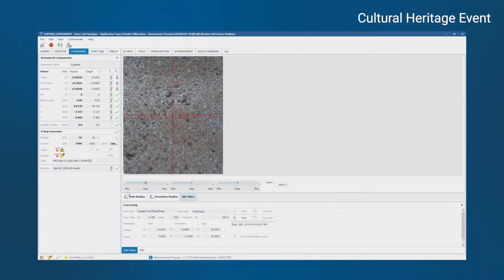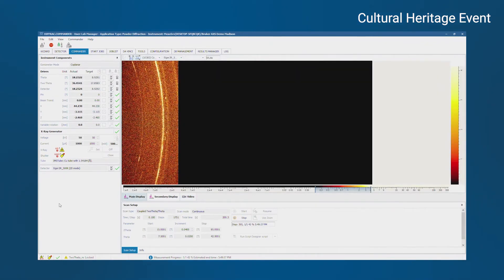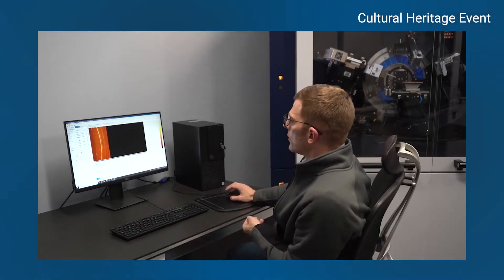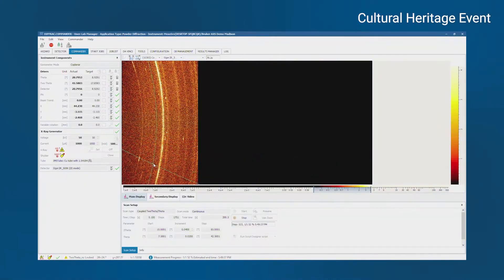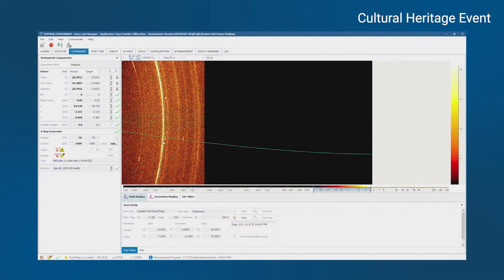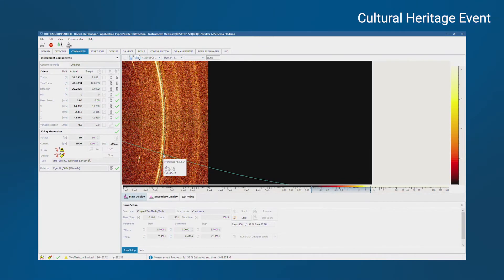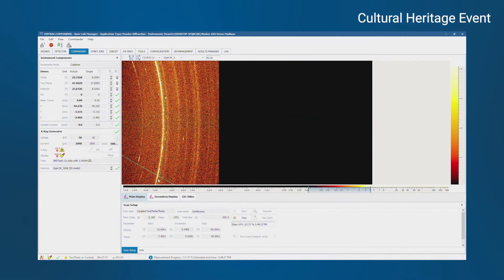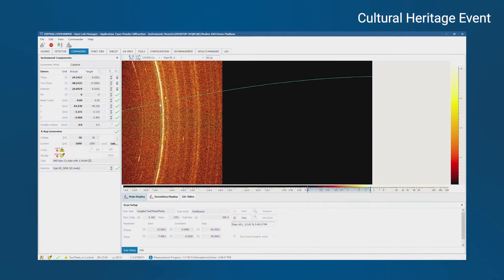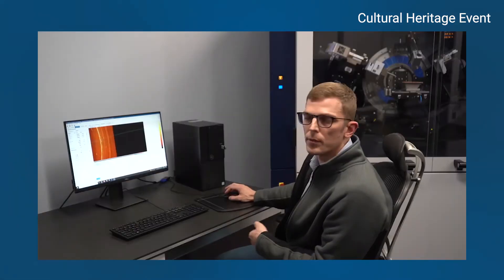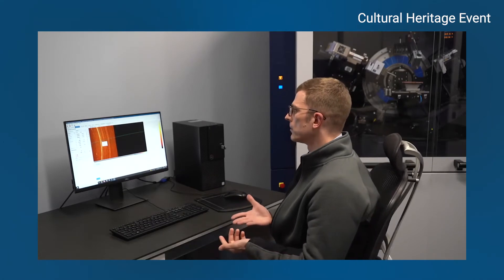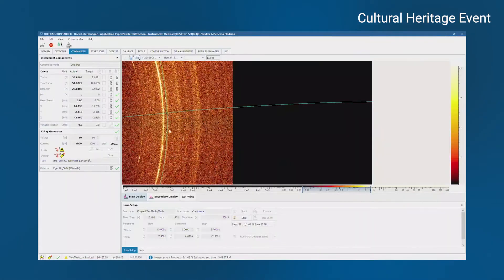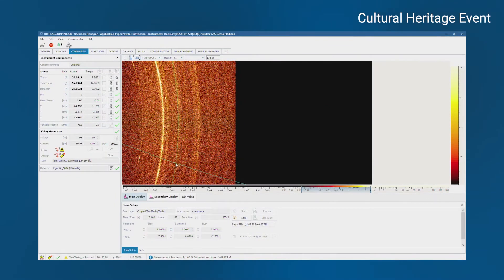If I go back to the main display, we should see some of the image. Essentially what you have in 2D diffraction is diffraction rings rather than diffraction peaks. Instantaneously, you can see just by looking at how filled in the rings are, if you have sufficient sampling to get accurate phase identification. Here it's a little bit spotty, so maybe we don't have quite enough crystallites. But then this ring is very filled in, so this one is probably going to give a very accurate peak intensity. This is more information than you could get doing a traditional XRD scan. And it's nice to get some confidence in the data.